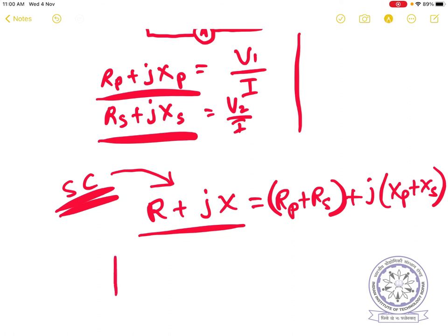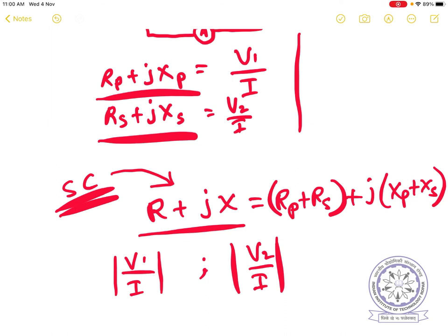Instead of just magnitudes, using V1/I and V2/I from the short circuit test, and assuming the phase angle is the same for both primary and secondary impedances, we can divide R + JX into its primary and secondary components. This is how the separation of impedances is accomplished for the transformer equivalent circuit. Next, we will look at exciting current in the next class. Thank you.